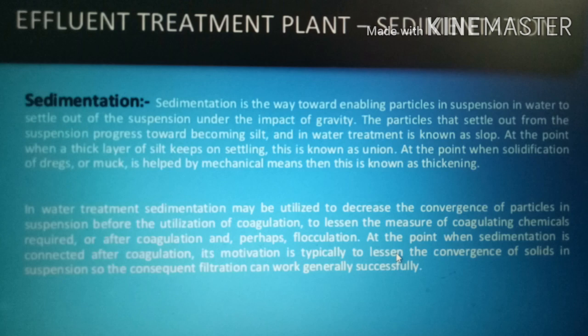So in water treatment, sedimentation may be used to reduce the concentration of particles in suspension before the application of coagulation, to lessen the amount of coagulating chemicals required, or after coagulation and possibly flocculation. When sedimentation is applied after coagulation, its purpose is typically to reduce the concentration of solids in suspension so the subsequent filtration can work most successfully.